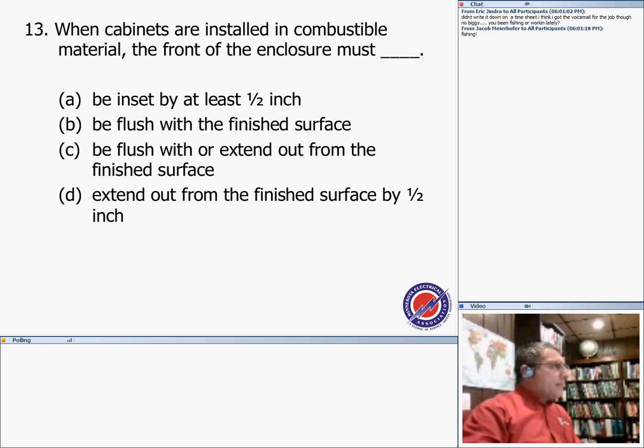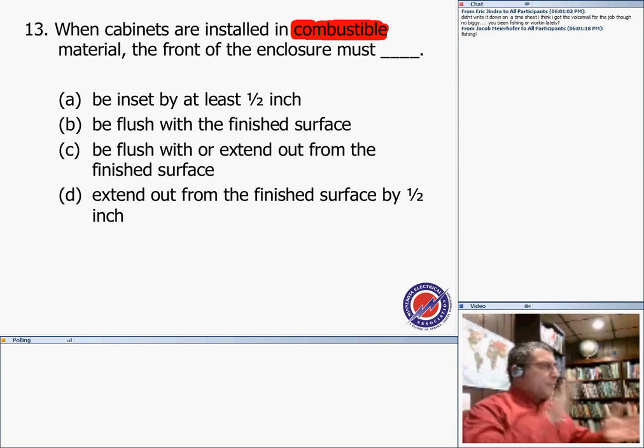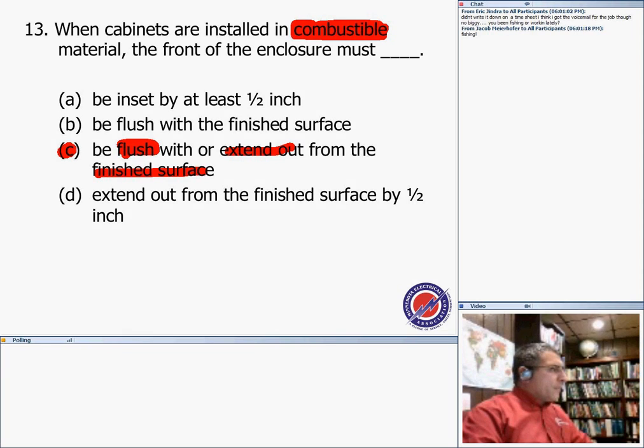Just when installed into combustible materials, the front of the enclosure. Now remember, it's combustible, so they don't want anything. If flame and spark and arc inside this box, they don't want it to spread, so they want it to be completely shut by the cover. So our answer for number 13, my friend, was C. I'll tell you why C, guys. Be flush. That's one, or extend out from the finished surface. So you can have it.